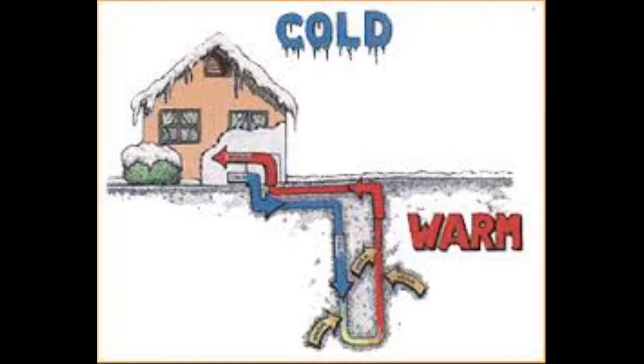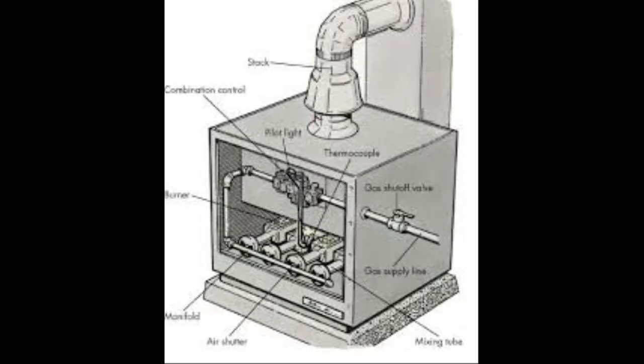The water now leaves the heat exchanger at a colder temperature and circulates through the earth loop to pick up more energy. The refrigerant gas, which contains energy gained from the earth loop, travels to the compressor. In the compressor, the refrigerant temperature rises to 160 degrees. The superheated refrigerant leaves to the air heat exchanger. Here, the heat pump's blower circulates air across the air coil, increasing the temperature of the air, which is blown through the ductwork to heat the home. After the refrigerant releases its heat energy to the air, it then flows to the earth loop heat exchanger to start the cycle again.